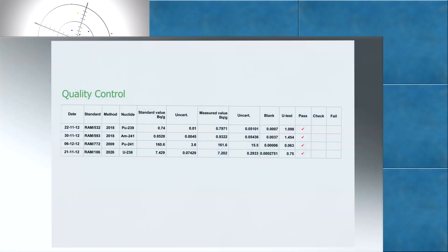RADEC LIMS incorporates a range of quality control functions using QC data entered by the analyst. Data are compared with the integrated reference sample or standards database, and are then quality assessed based on the statistical U-test.